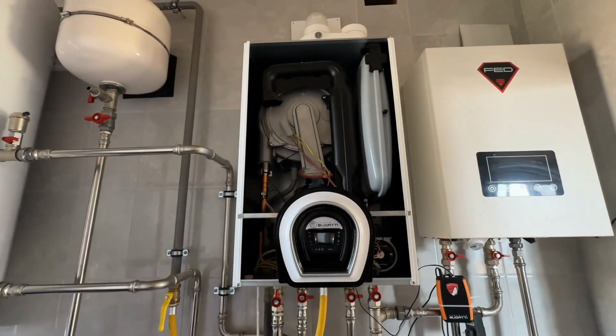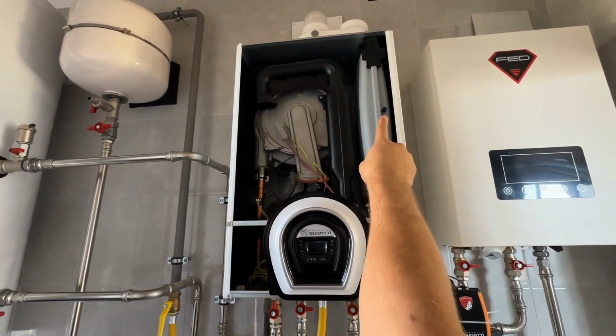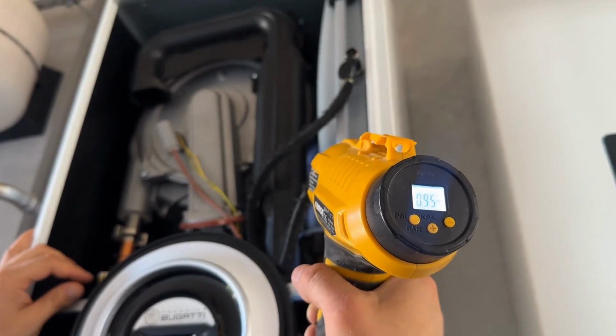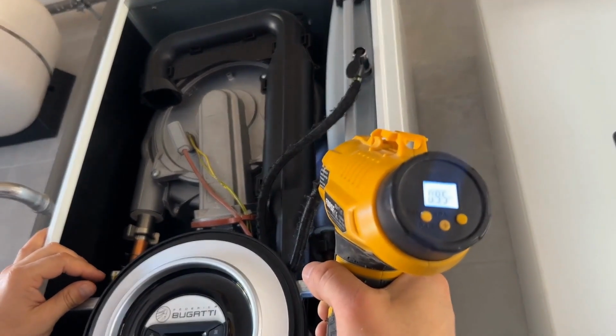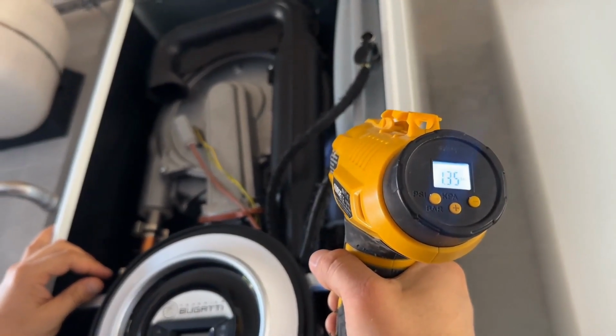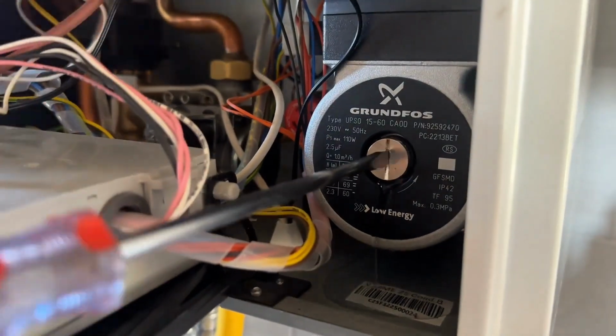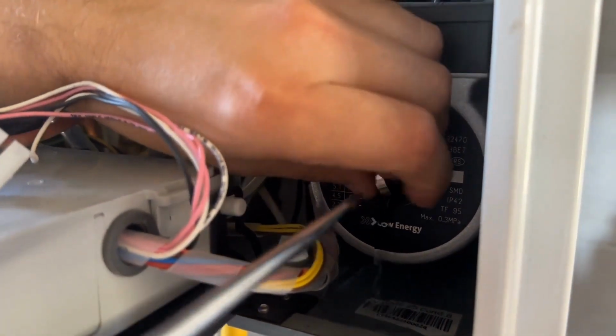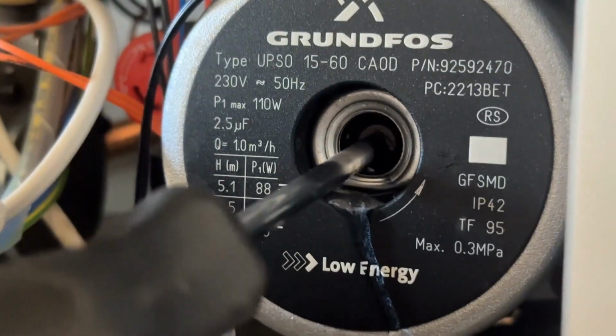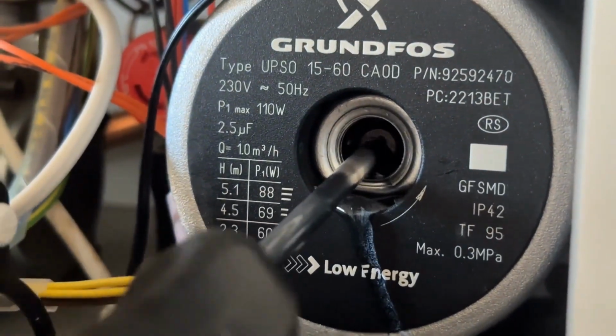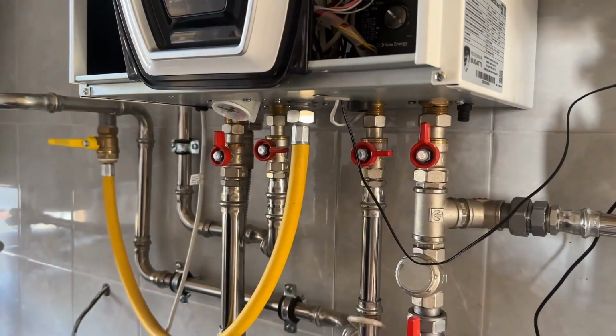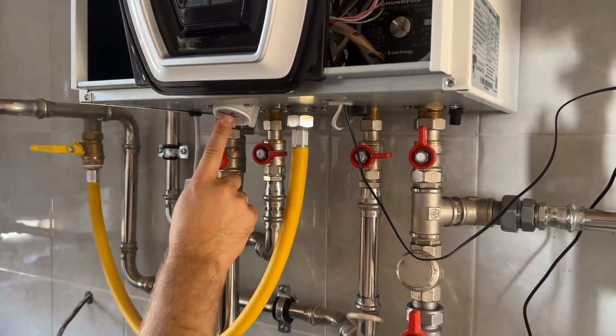Before filling, it is necessary to check the pressure in the expansion tank. You can pump up the expansion tank if the pressure is not satisfactory. It is very essential to ensure that the pump shaft rotates smoothly and freely. After that, we open the heating system and replenish the pressure according to the manometer.